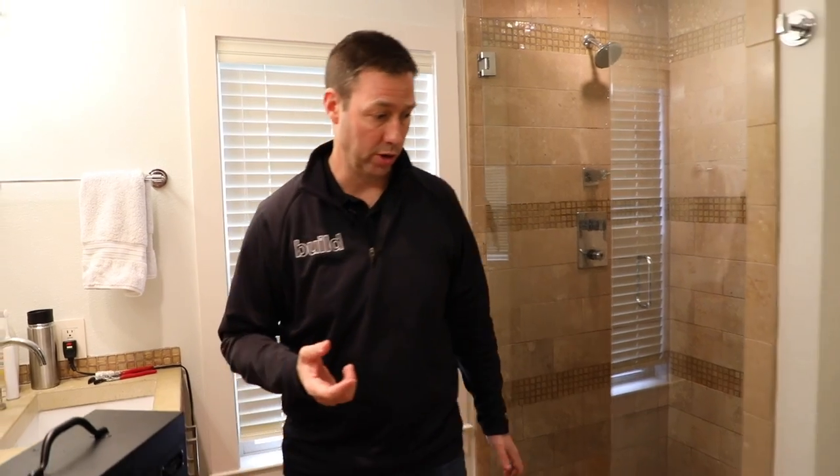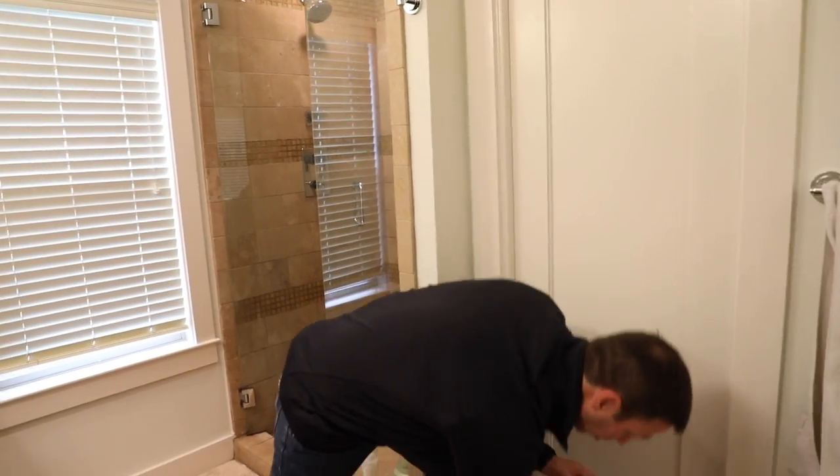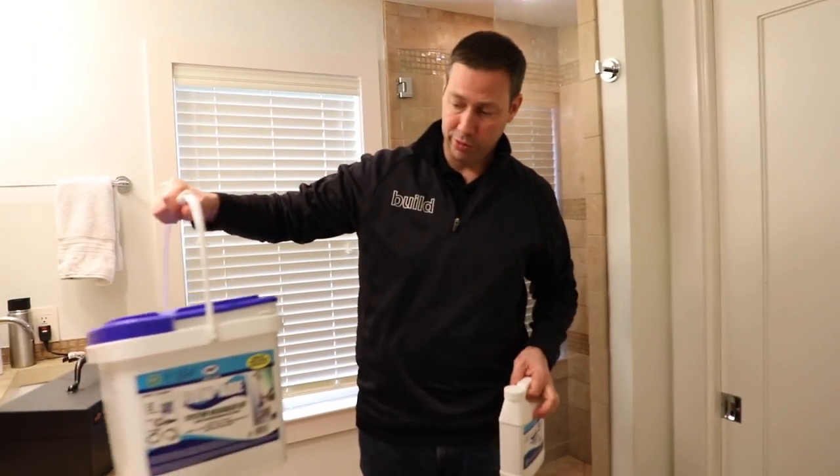So it's probably scaled up so much that it threw off this scale into the system, and now that's why he's got low flow problems — the calcium carbonate is clogging things in the system. So there's two things we're going to do here. Number one, we're going to actually maintain and flush his system. I brought my little flush kit with me.